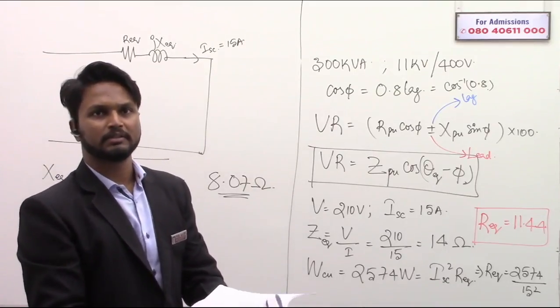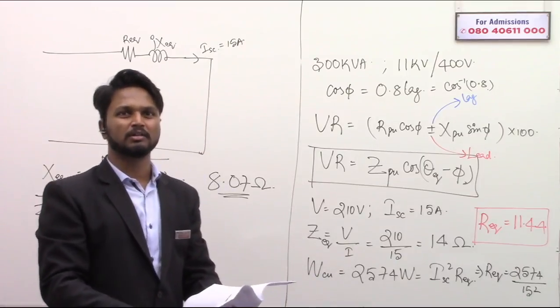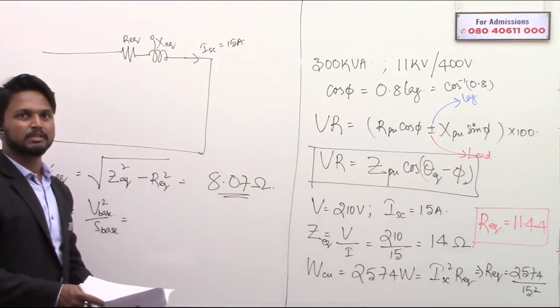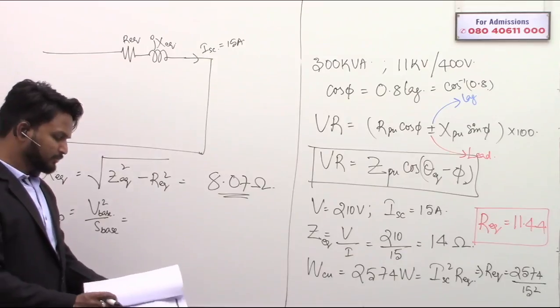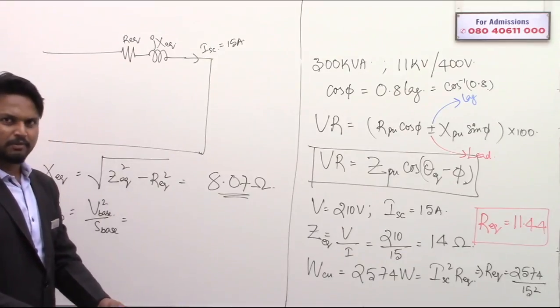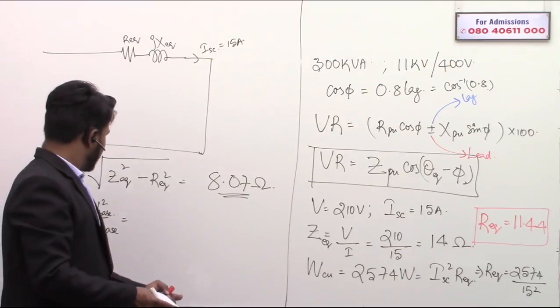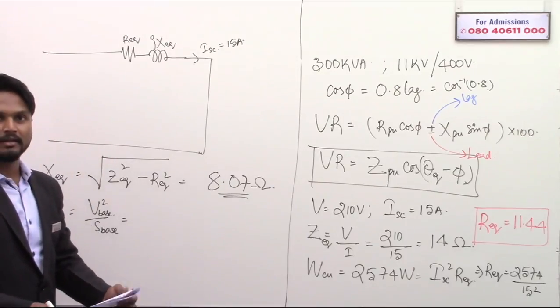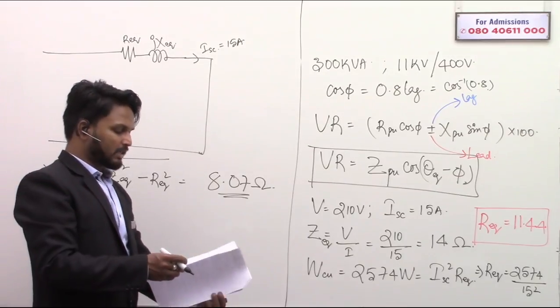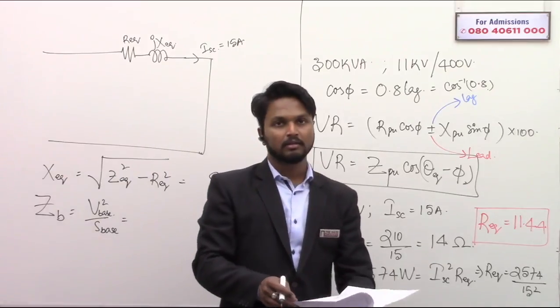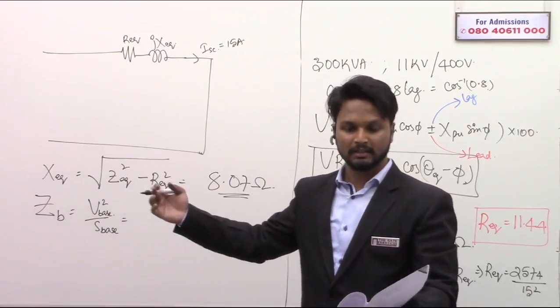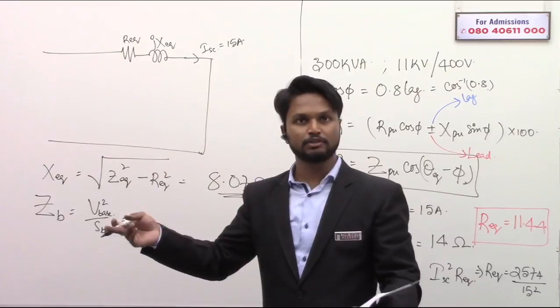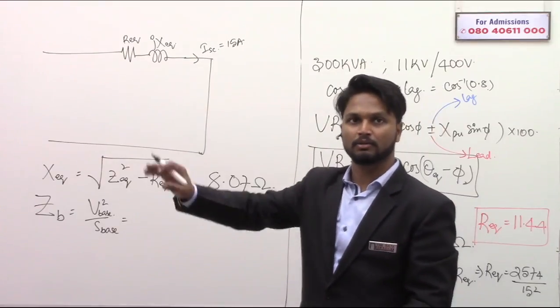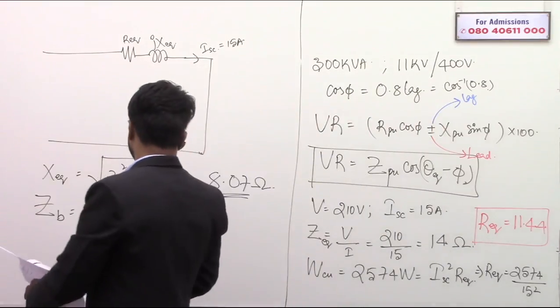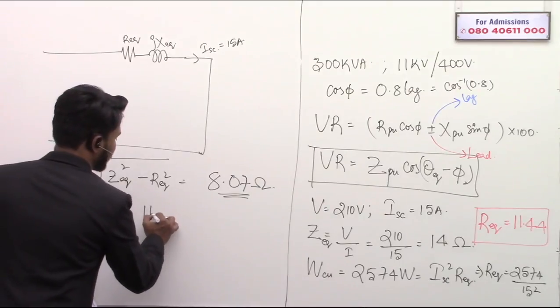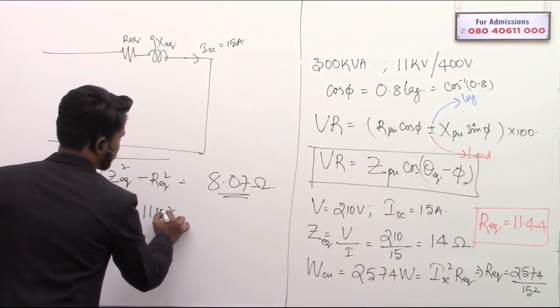Lakshmi Narasimhan, you got it wrong. There's a mistake in your answer, so just check for calculation errors. The base voltage is the rated voltage. On what side are you performing this test? You have connected the supply to which side? LV is shorted, which means HV is connected to the supply side. The HV side voltage is 11 kV square.